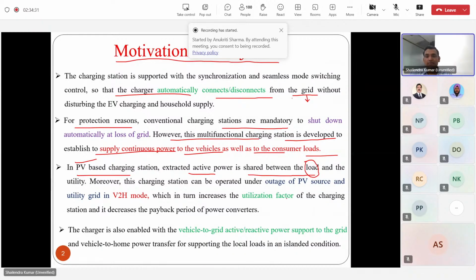Moreover, this charging station can be operated under outage of PV source and utility grid in vehicle-to-home mode, which increases the utilization factor. What we found is that in a simple conventional charging station, if the utility grid is not there, the utilization factor of your power converter is very low - you have to shut down at that moment, and you won't get any power to your onboard or off-board chargers.